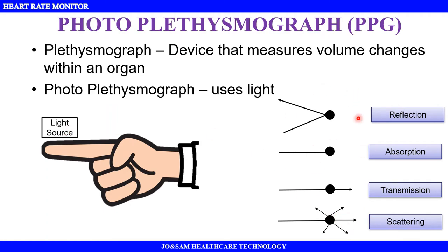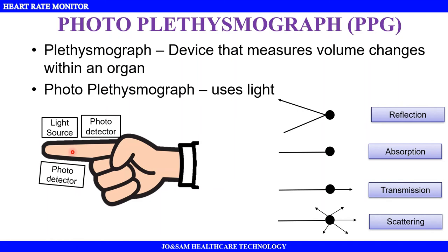With all these processes occurring in the finger, once the light source illuminates, it will reflect. We measure the reflected light using photo detectors placed alongside the light source — that is the reflectance method. In the transmittance method, the photo detectors are placed on the opposite side to measure scattered and transmitted light.